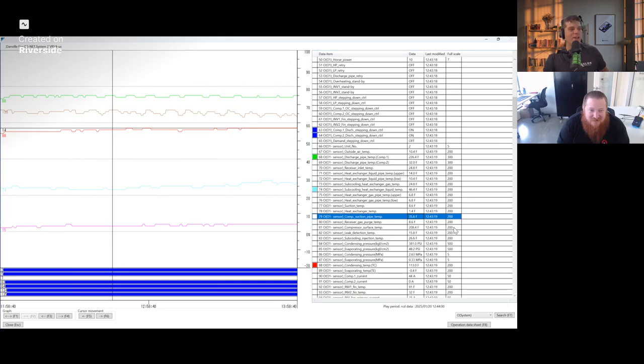That's the thing, guys, right? Just because it's on the liquid line and you say, well, look at it, I am subcooling the F out of this refrigerant. It's like, no, you're not. Your liquid turned to a vapor in your liquid line, and it made it all the way back to the outdoor unit, and it's still continuing to change states as it goes through.